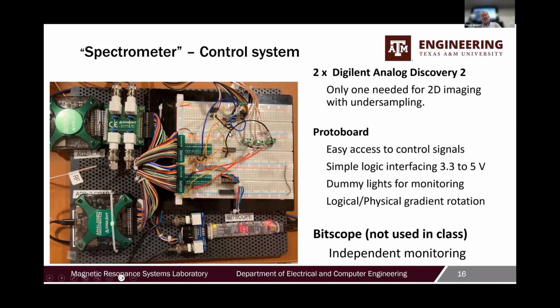But you have to have a little additional hardware because the AD2s are 3.3 volts. The attenuator uses 5-volt logic. So we had to convert that with an inverter chip. This is where the gradients connect, X, Y, and Z. And the fly wires are a poor man's ability to change imaging orientation by just moving around which gradient goes to which physical coil, the X, Y, or Z. So it's very nice. I can switch from sagittal to axial view by just swapping these 3 wires around.